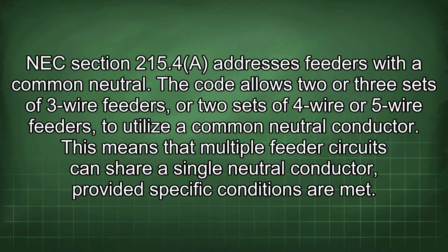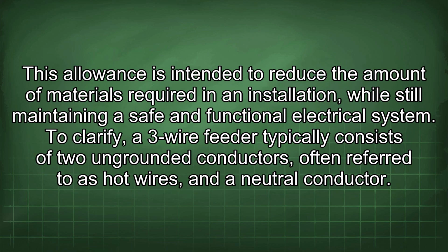NEC section 215.4 addresses feeders with a common neutral. The code allows 2 or 3 sets of 3-wire feeders, or 2 sets of 4-wire or 5-wire feeders to utilize a common neutral conductor. This means that multiple feeder circuits can share a single neutral conductor, provided specific conditions are met. This allowance is intended to reduce the amount of materials required in an installation, while still maintaining a safe and functional electrical system.